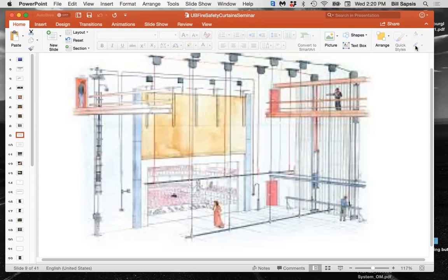There is an additional piece of equipment which we might as well touch base on now that is used in conjunction with a fire safety curtain, and those are smoke doors. Smoke doors are in most theaters, in different styles. Certainly the older theaters, the late 19th, early 20th century theaters, had a cupola on the roof with doors that would fall open, or slide open, if they were tripped. The theory there was you wanted to be able to evacuate all the built up heat and gases coming from the fire that were rising up in the stage house. And that's a really good idea because you can build up a lot of pressure there, and you run into a lot of difficult situations.